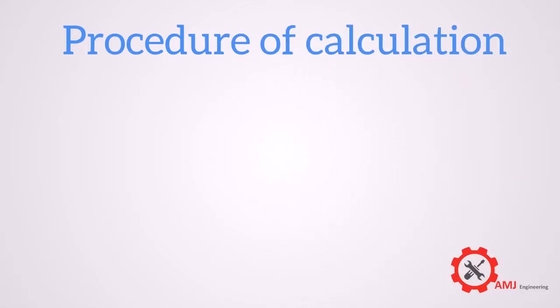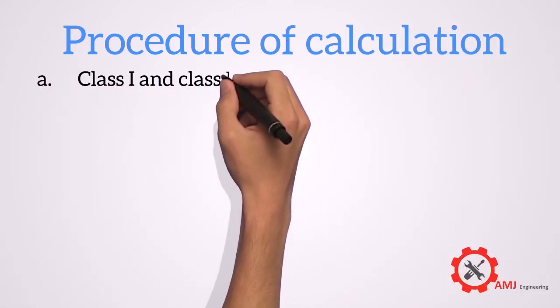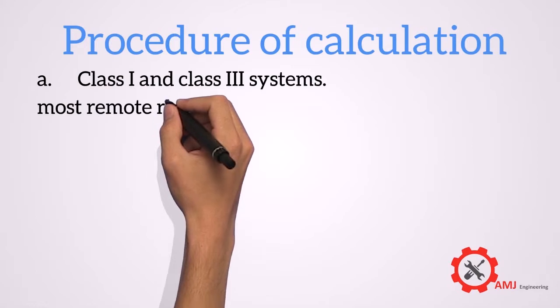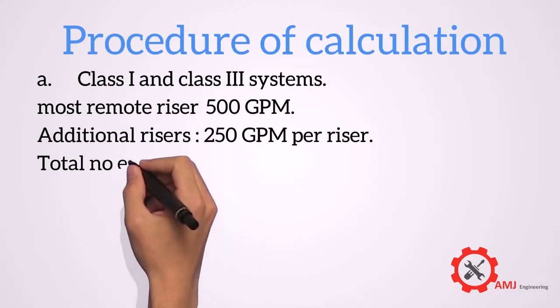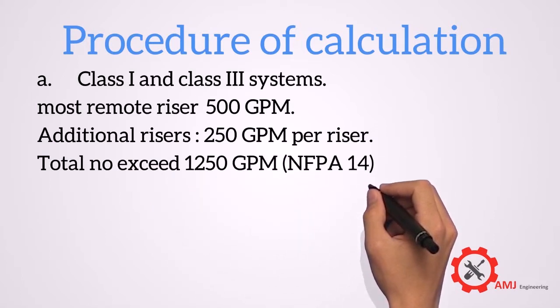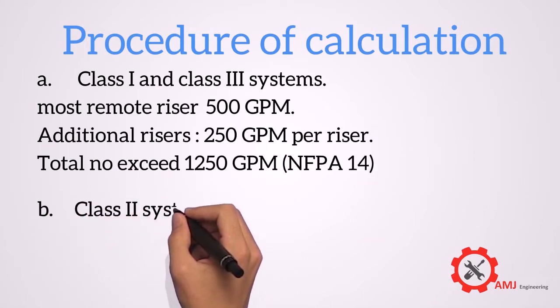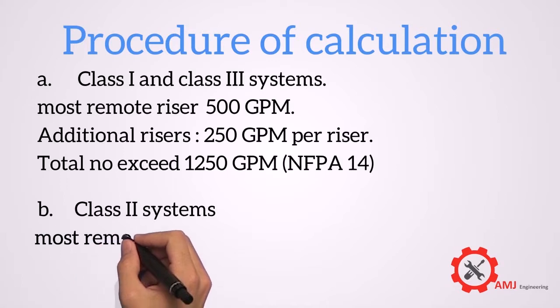Procedure of calculation is as follows. For class 1 and class 3 systems, the minimum flow rate for hydraulically most remote riser shall be 500 GPM. The minimum flow rate for additional risers shall be 250 GPM per riser, the total not to exceed 1250 GPM.